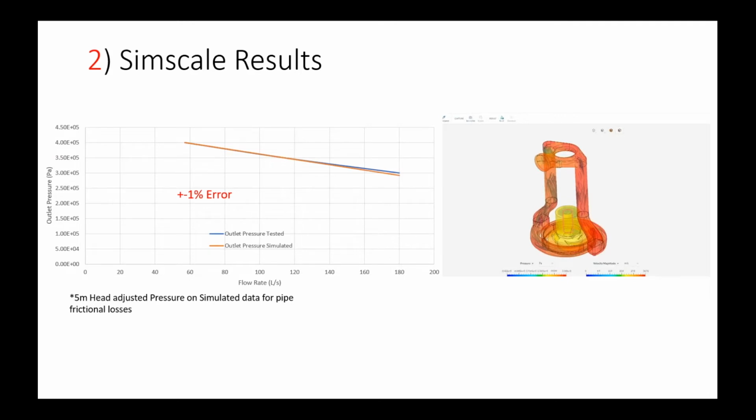Okay, so we ran the same pump and we plotted the data, and we saw that for some of the data points, it looked like the same line. The crazy thing over here is you expect about 2 to 3% difference because you have to allow for manufacturing differences. Manufacturing processes always deviate slightly from the theoretical model. So we expect about 2 to 3% difference. This is a special case.